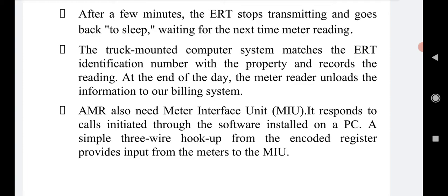AMR also needs meter interface units, meaning MIU. It responds to calls initiated through the software installed on a PC. A simple 3-wire hookup from the encoded register provides input from the meters to the MIU.